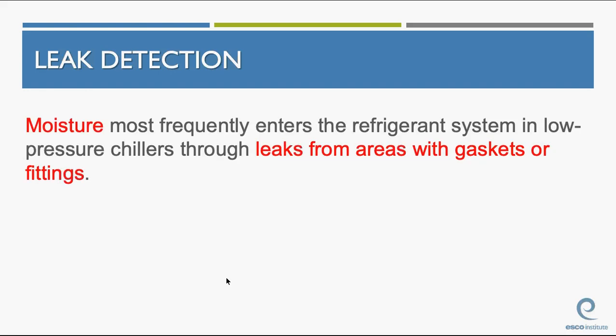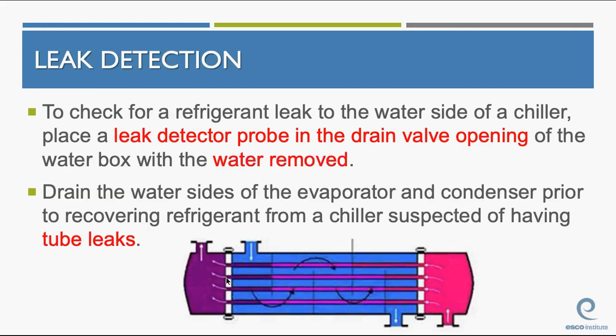Moisture most frequently enters the refrigeration system in low-pressure chillers through leaks from areas with gaskets or fittings. Guys, gaskets leak over time. These chillers could be in place for 20 or 30 years. Sooner or later, these gaskets are going to leak and need to be replaced. But anytime you have a leak in a low-pressure chiller, you've got to start checking the gaskets and the fittings, because that's where it happens.